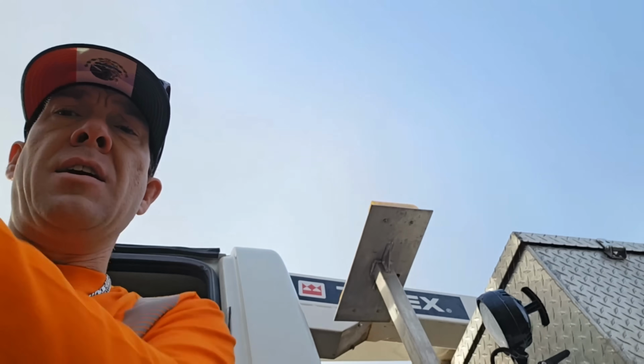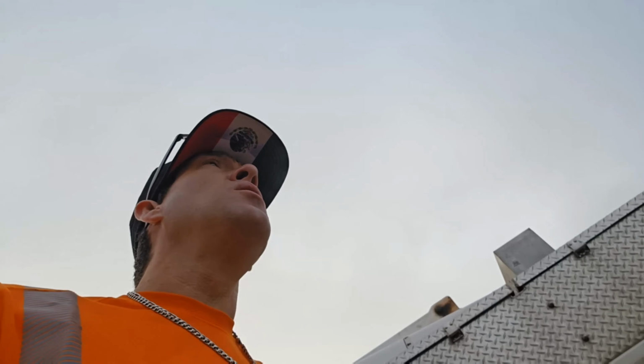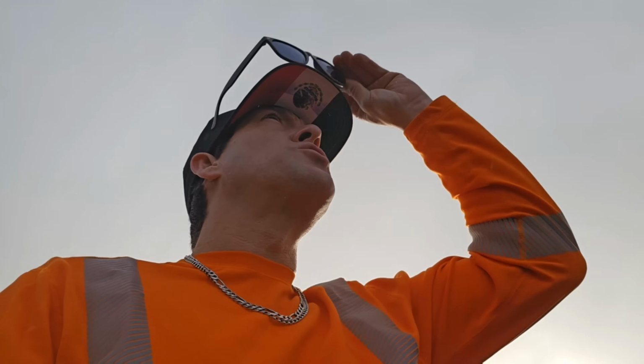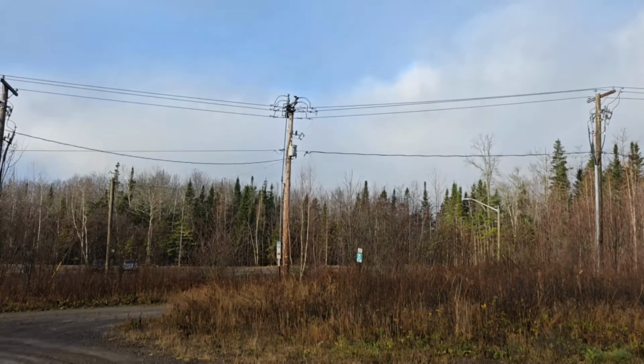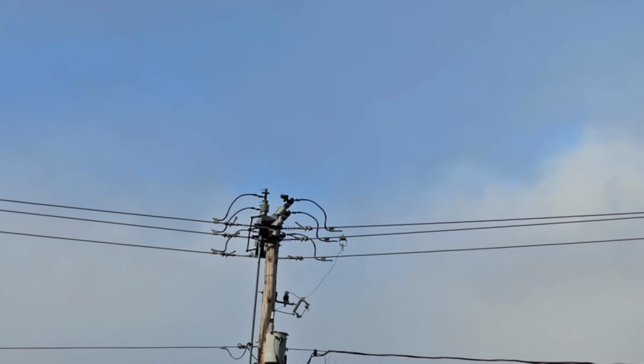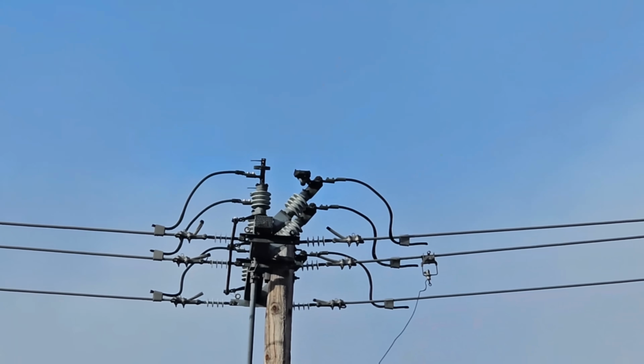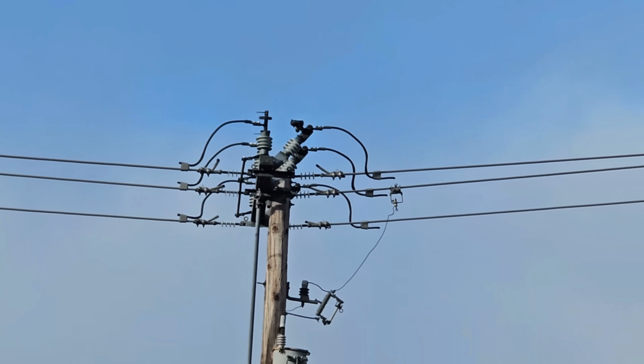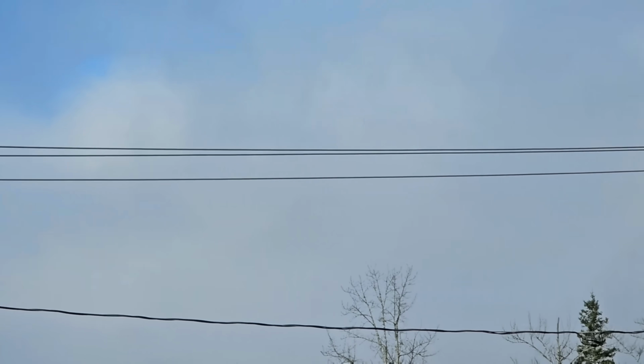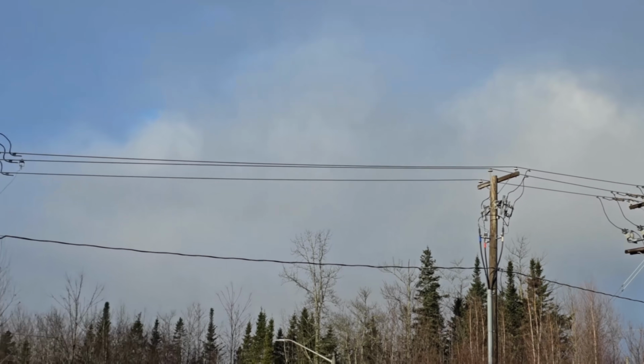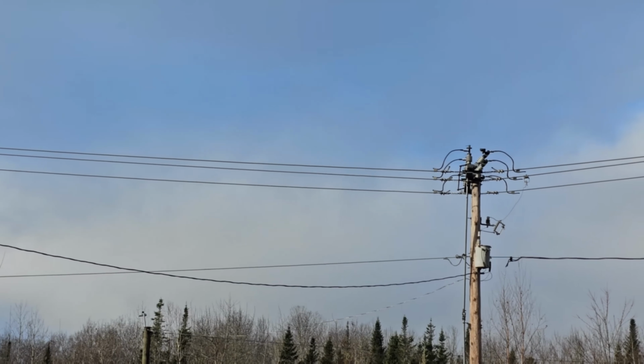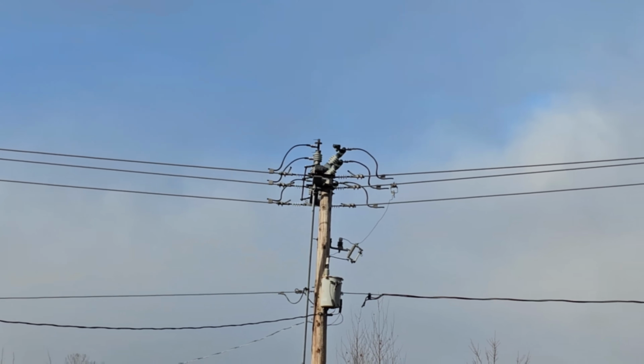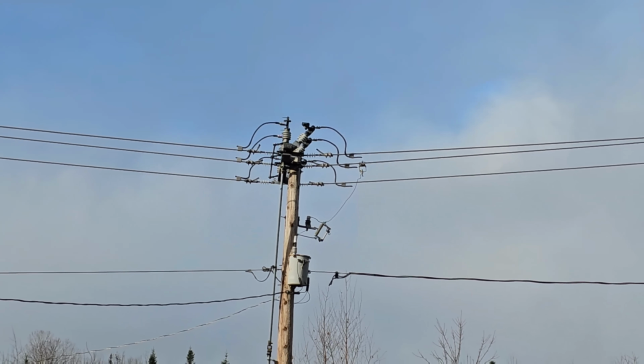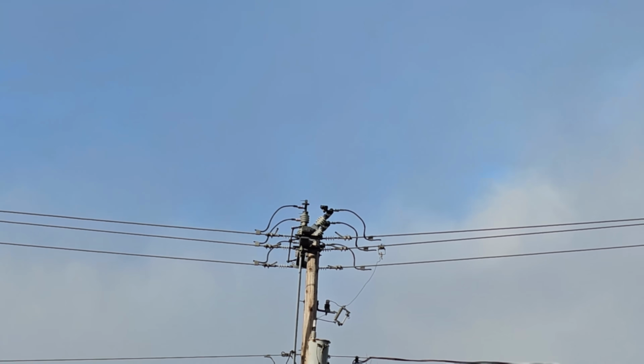We're at the other substation now, and before we go inside, I'll show you this. This is an example of one of the switches out in the field. You can see there's a gap there, it's open. That's a device we can close in. Let's say this power comes from the other substation and these customers on the left are out of power. We can close that switch to tie the left grid to the right grid.